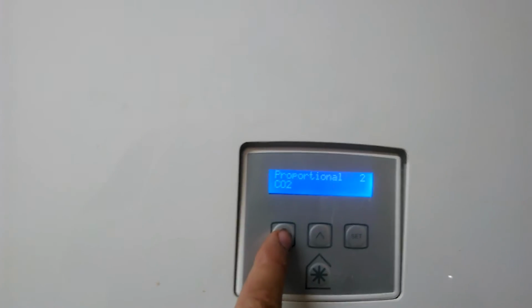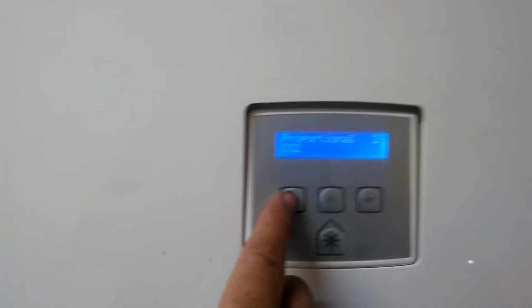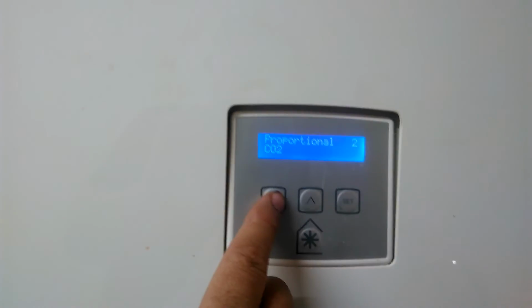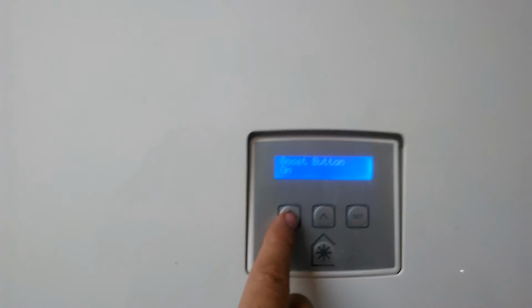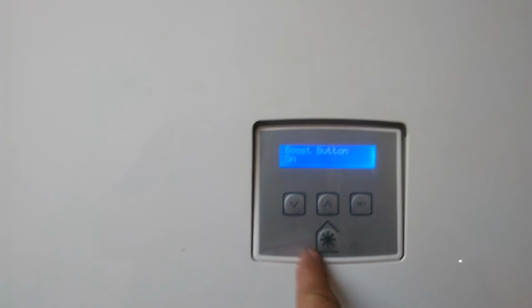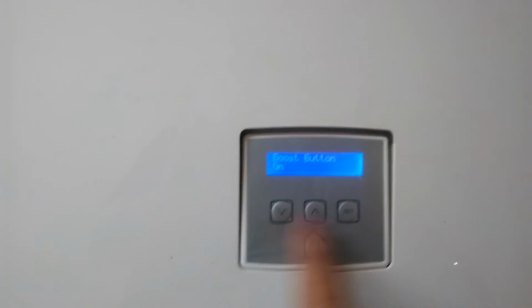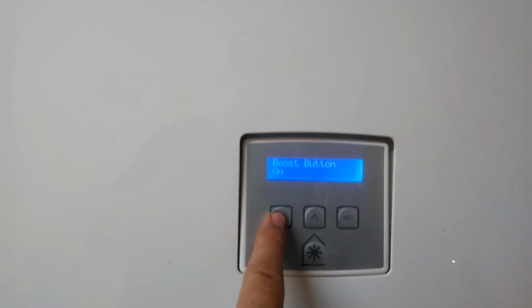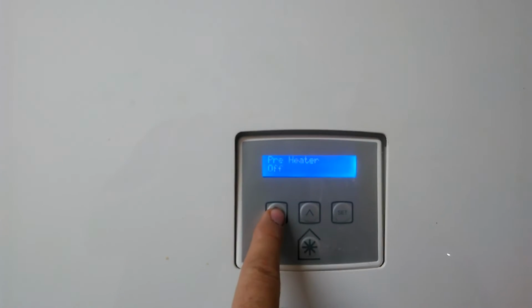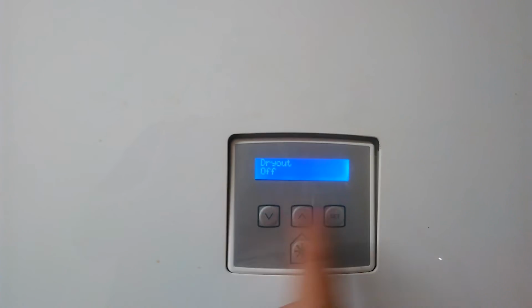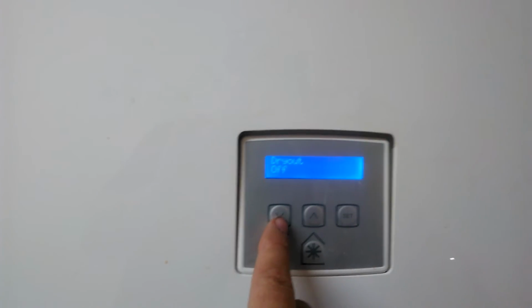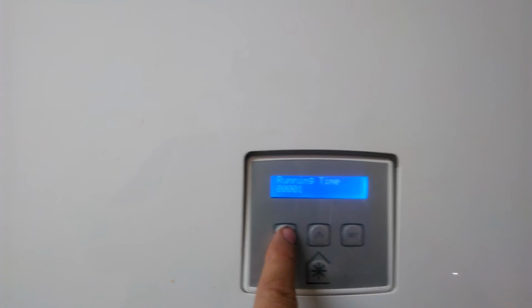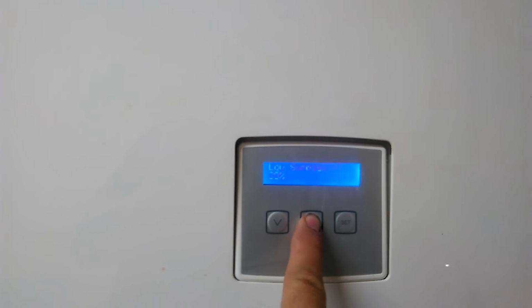These proportional screens are, if we have other switches, you can have a CO2 switch, and you can have other humidity sensors as well, let's say if it was in changing rooms. Okay, but this one, we just relied on the internal humidity. Momentary, we're not bothered about that. Boost button's been assigned to this house with a snowflake in the middle, so that's on. So if you press that, it goes into boost. Summer bypass is fitted on this machine. No preheater on this. This dryout mode, that's really if you want to dry your house out, but not recommended in dusty building environments. Okay, let's get out of these screens.